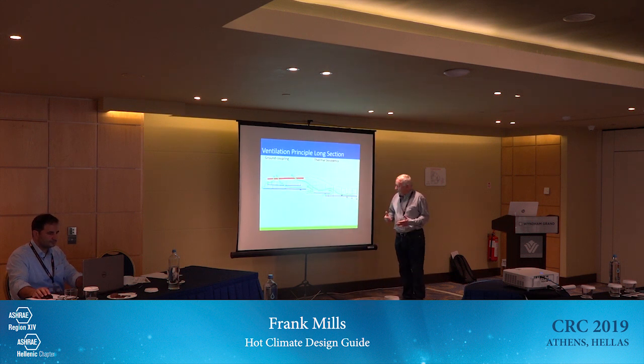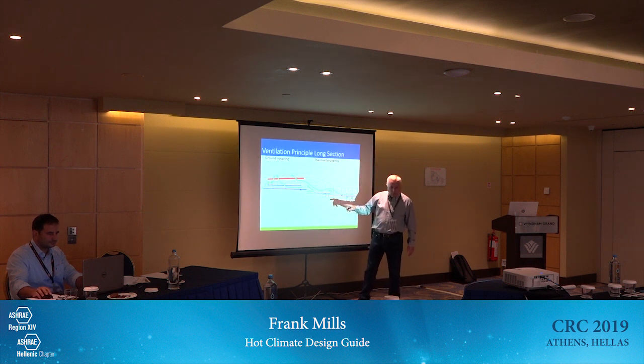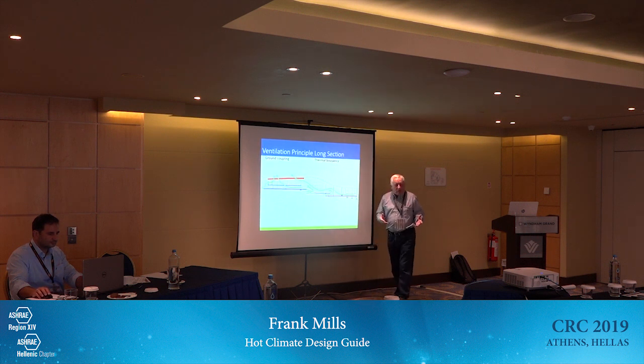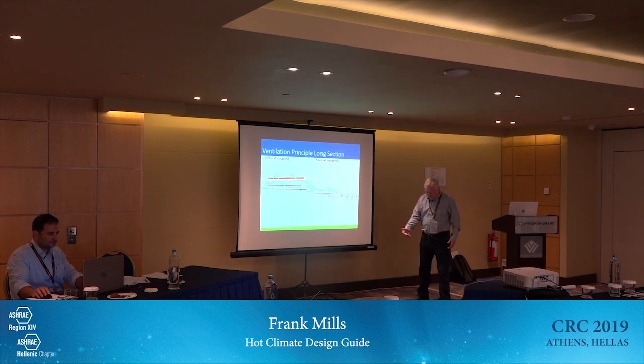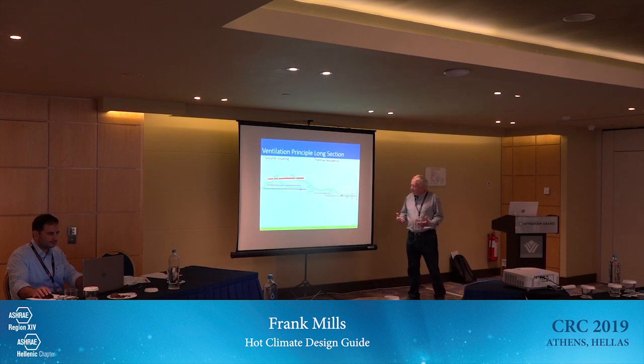So what I'm saying is originally this building was back here, this was dug out, so we had a retaining wall, a slab up to here. Retaining walls are expensive, of course. You've got a rainwater problem, because water's trying to push through, so you've got to keep them waterproof and all that kind of thing. But if you slip it forward, then suddenly this is not a retaining wall, it's just a wall. And this is a spare void underground where you can bring the air in along underneath the building. It's linking with the ground. So the ground is always about 10 to 15 degrees centigrade, that's the kind of temperature, all year round.